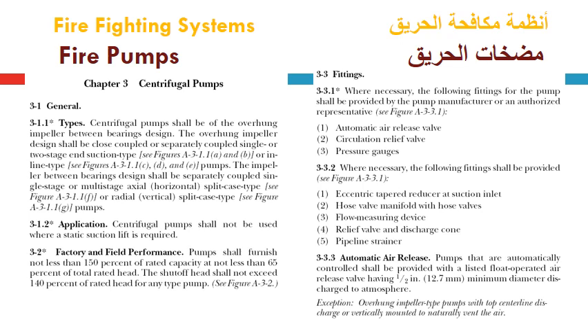Application: centrifugal pumps shall not be used where static suction lift is required. So it means a static suction head should be provided, as will be shown in next slides. Factory and field performance. Pumps shall furnish not less than 150% of rated capacity at not less than 65% of total rated head. The shut-off head shall not exceed 140% of rated head for any type of pump.